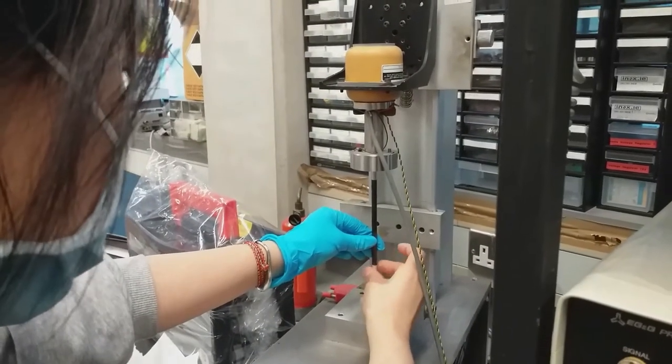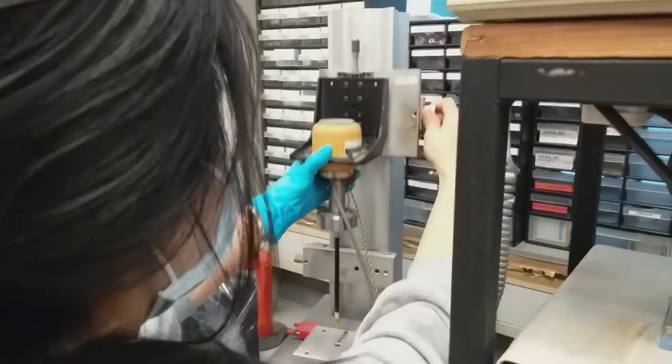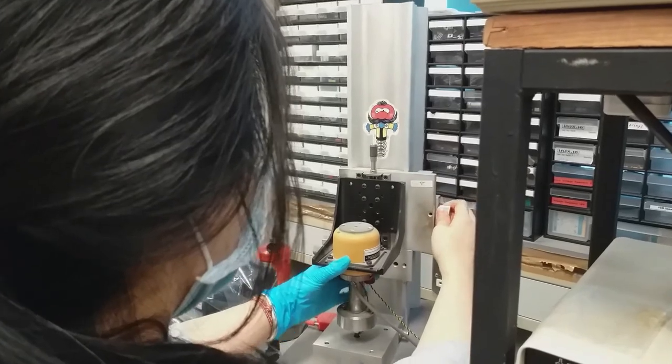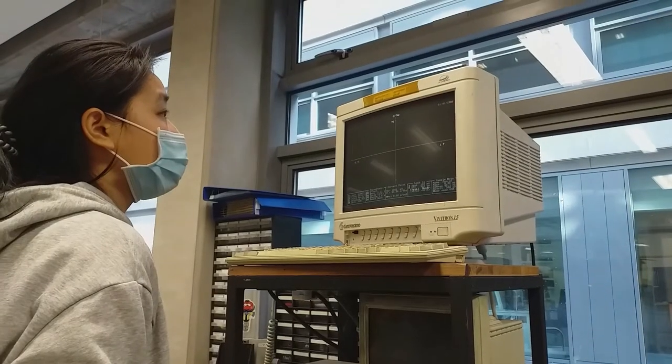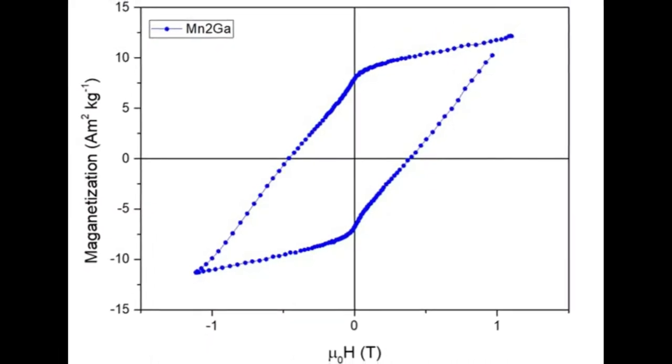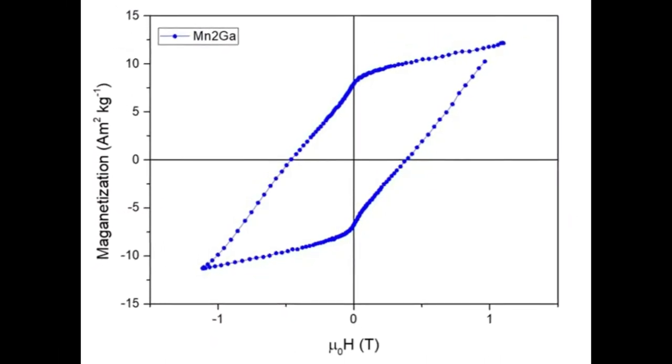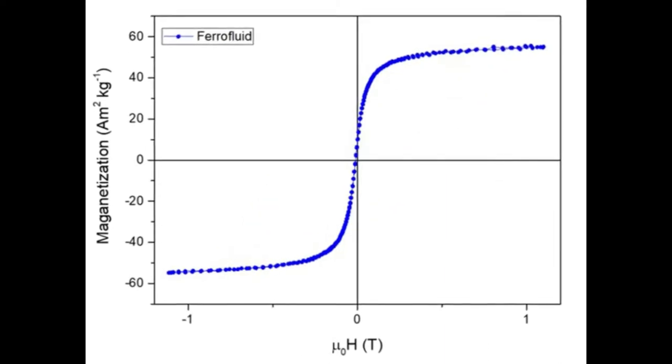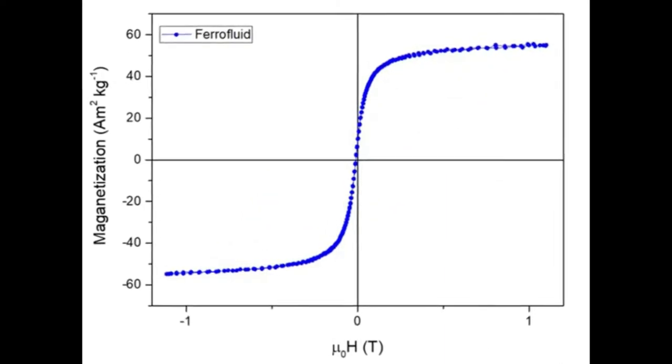After the calibration, now we can load the sample we have prepared, following the program guidelines to finish the M vs H scanning. Here, there are two types of loops we have measured. One is manganese-gallium which shows a high hysteresis loop. The other one is ferrofluid which shows just a small hysteresis.